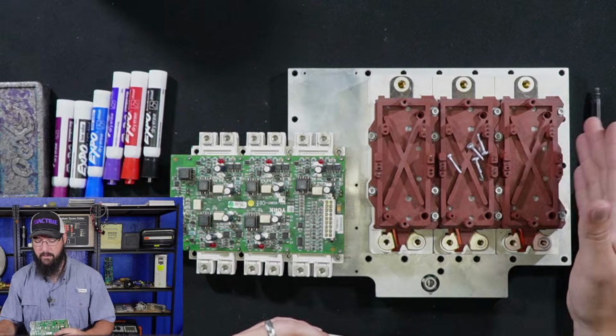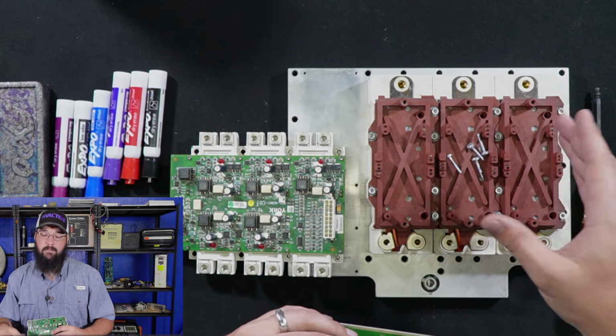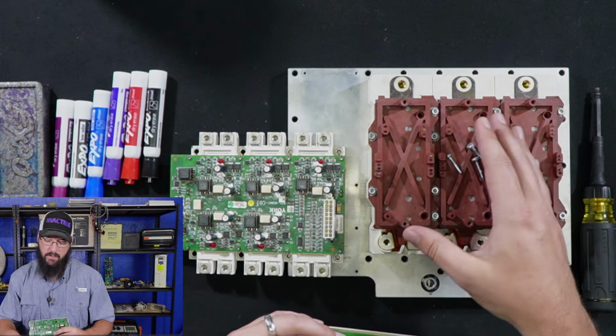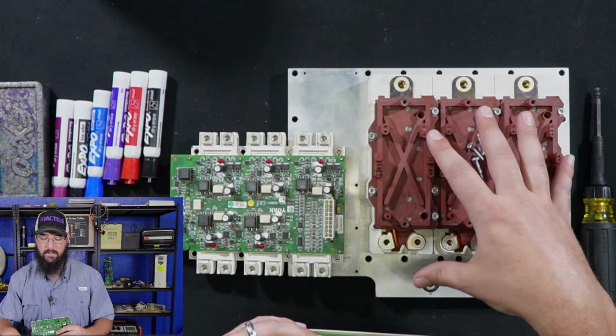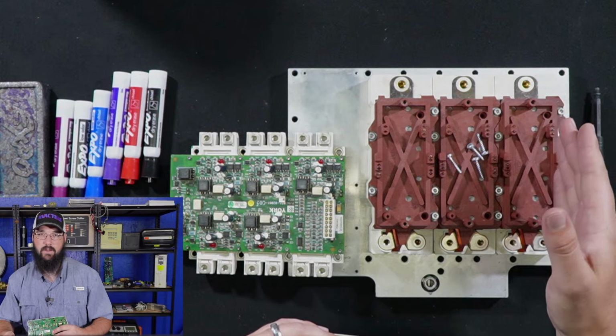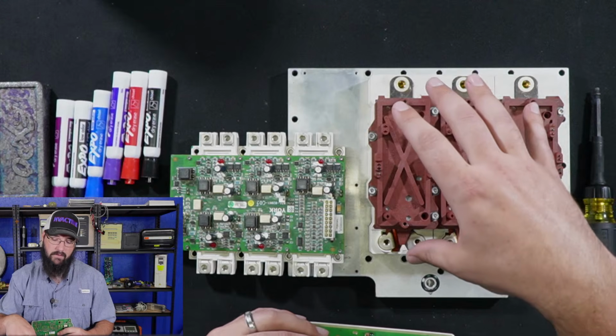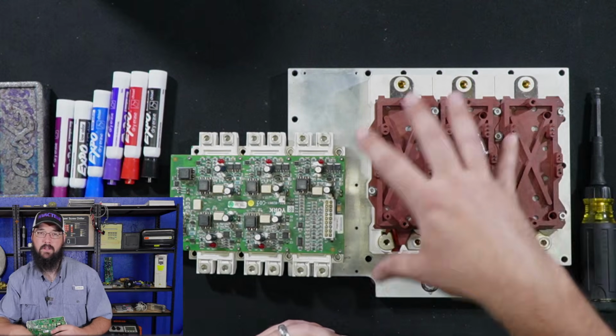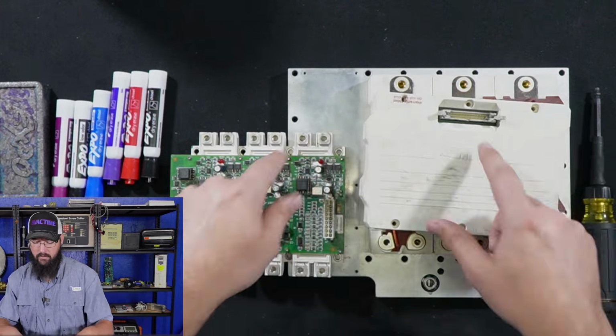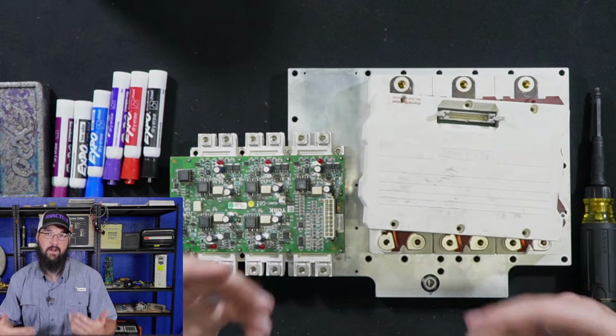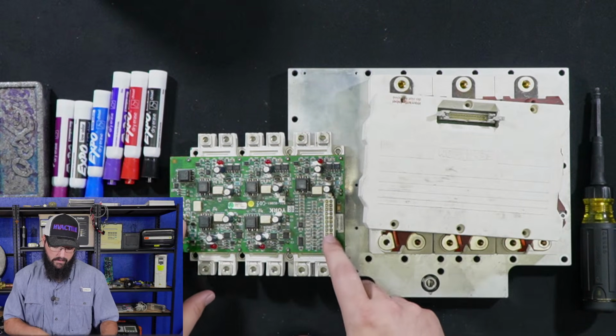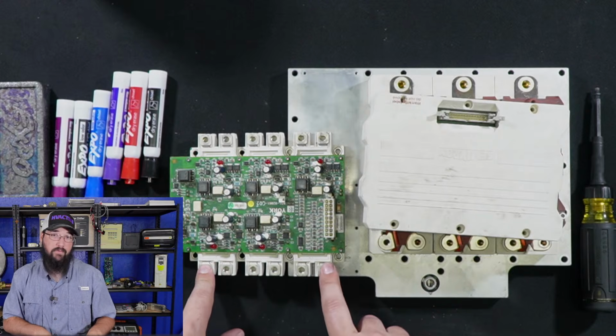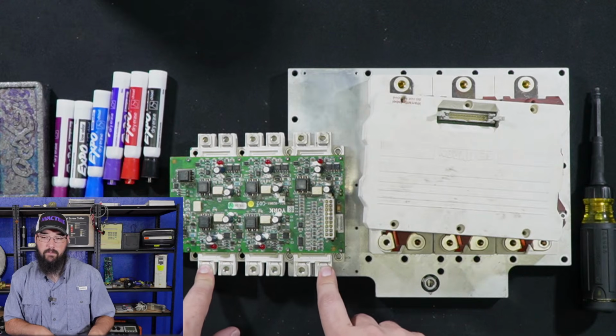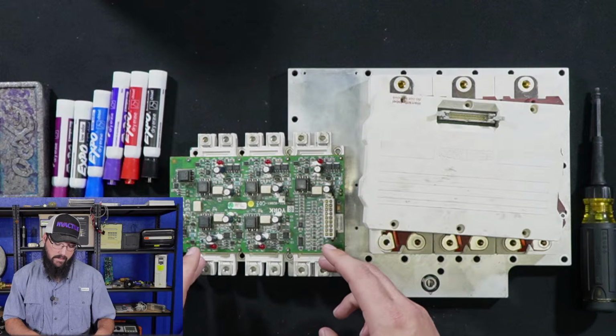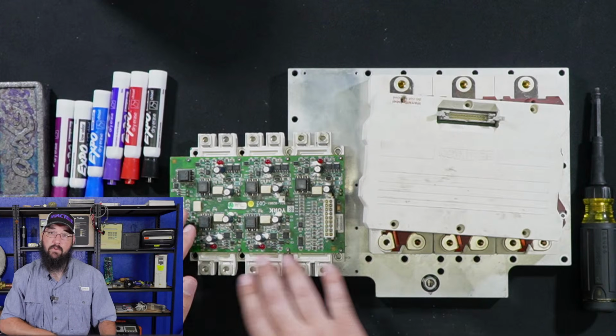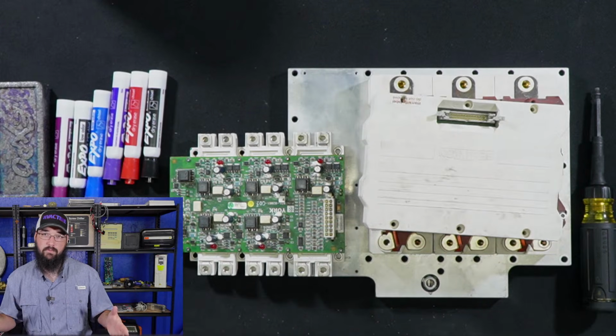Again, this is a three module bank or assembly where we've got three different sets of IGBT modules built into one master assembly. So this is telling those how to fire and trigger in order to run. These could be run in three-phase where they're 120 degrees out from each other, or they could be run as a single phase of a larger three-phase assembly.